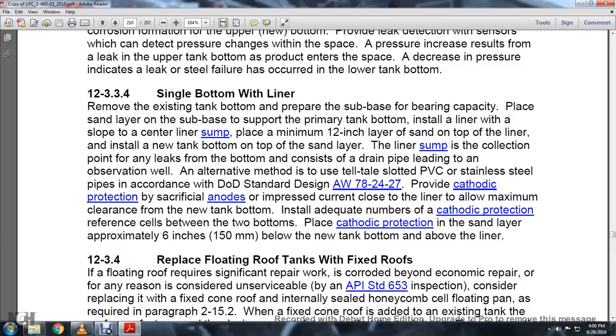Section 12-3-3-4: Single bottom with liner. Remove the existing tank bottom and repair the sub-base to adequate bearing capacity. Place a sand layer on the sub-base to support the primary tank bottom. Install the liner with slope toward the center sump. Place a 12-inch sand layer on top of the liner and install the new tank bottom on top. Leak collection at the bottom consists of a drain pipe leading to an observation well, or telltale PVC or stainless steel pipes per DoD Standard Design AW 78-24-27. Provide cathodic protection with sacrificial anodes and impressed current. Install cathodic protection reference cells approximately 6 inches below the tank bottom, above the liner.